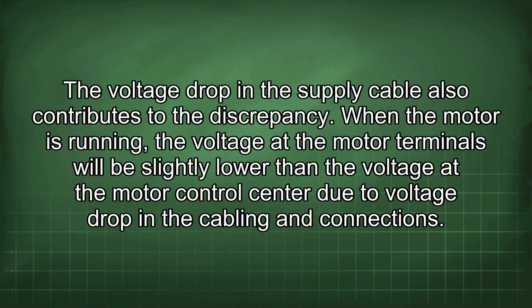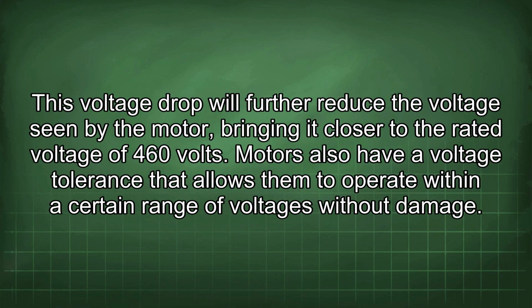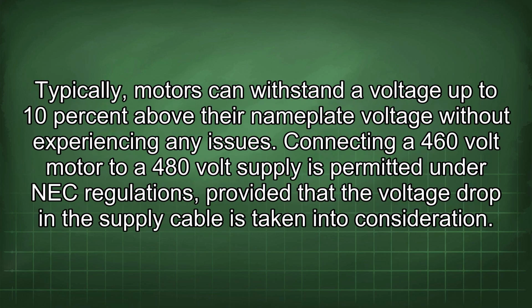The voltage drop in the supply cable also contributes to the discrepancy. When the motor is running, the voltage at the motor terminals will be slightly lower than the voltage at the motor control center due to voltage drop in the cabling and connections. This voltage drop will further reduce the voltage seen by the motor, bringing it closer to the rated voltage of 460 volts. Motors also have a voltage tolerance that allows them to operate within a certain range of voltages without damage. Typically, motors can withstand a voltage up to 10% above their nameplate voltage without experiencing any issues.